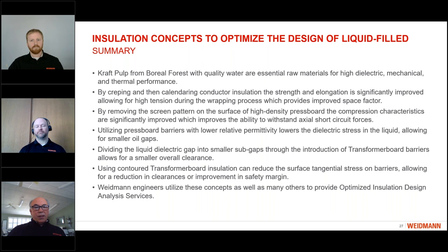So the next concept is the concept of lower relative permittivity. When you look at the oil paper dielectric system, the strength of the oil is much lower than the strength of the pressboard, by probably 5 to 1. So what ideally you want to do is to put more of the electric stress into the solid insulation. And one way that you can achieve that is if the solid insulation has a lower relative permittivity. If that relative permittivity approaches the relative permittivity of the liquid, then more of the stress will be transferred from the liquid to the solid, which is more capable of handling it.